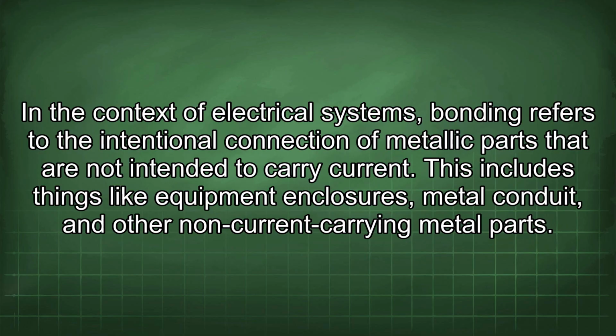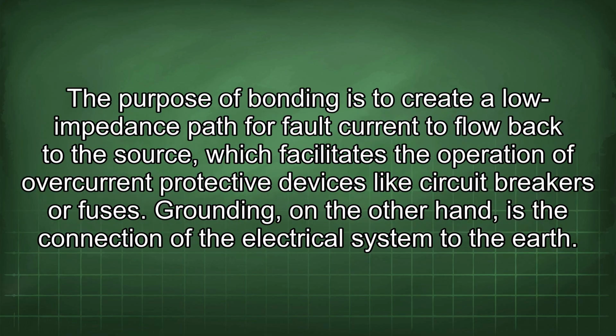In the context of electrical systems, bonding refers to the intentional connection of metallic parts that are not intended to carry current. This includes things like equipment enclosures, metal conduit, and other non-current carrying metal parts. The purpose of bonding is to create a low impedance path for fault current to flow back to the source, which facilitates the operation of overcurrent protective devices like circuit breakers or fuses.